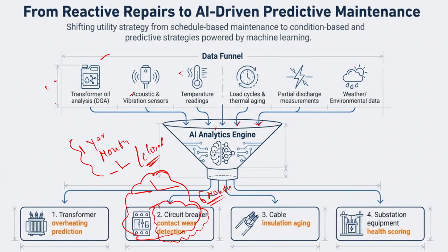So here if you observe, we are not waiting for the circuit breaker to fail, correct? We are proactively scheduling the maintenance of this specific breaker. So when we know that exactly on the 6th month we have to do the maintenance, we can proactively ask the substation to take the downtime, and inform the customer or the industry 1, 2 or 3 days before, telling that there will be downtime, so that the customer or industry can plan accordingly, instead of suddenly breaking a certain feeder, and this might affect the productivity, and also this might affect the consumers, right? So for that reason, we are doing the predictive analysis here, right?